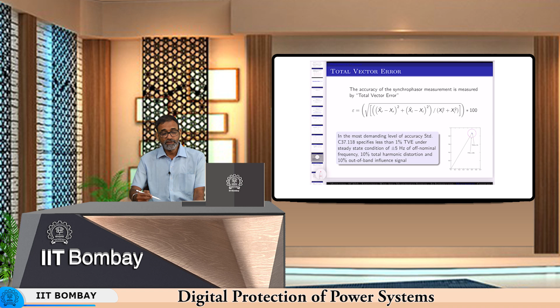Okay. So, here what it says is that the standard IEEE C37.118 specifies the most stringent level is 1% TVE under the steady state condition of plus minus 5 Hz off nominal frequency, 10% total harmonic distortion, and 10% out of band interference signal. Okay, so 10% total harmonic distortion, 10% out of band, whatever is the band, we will see what that is. And then under these conditions it should meet 1% TVE.